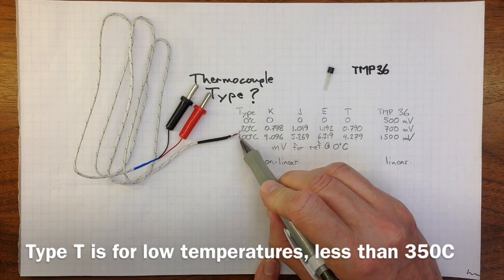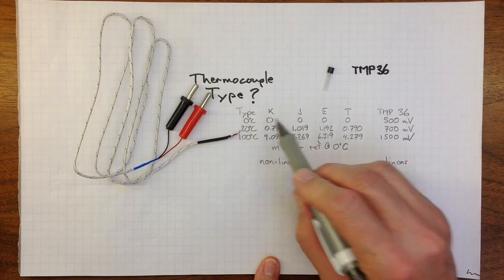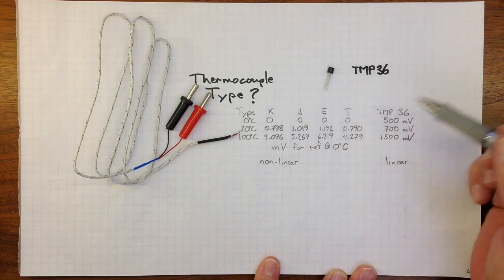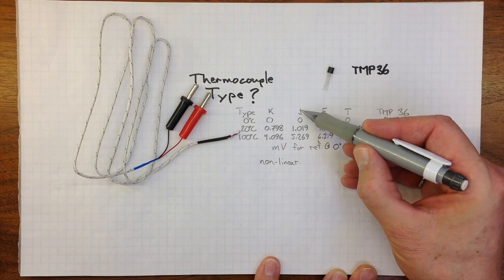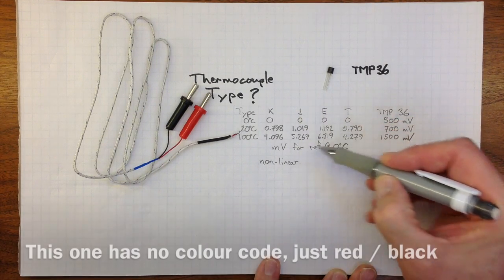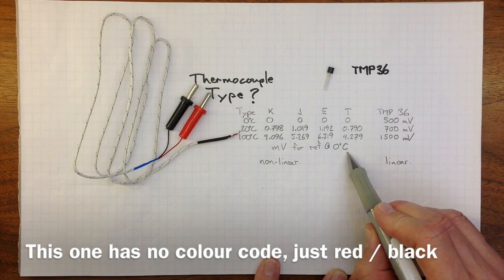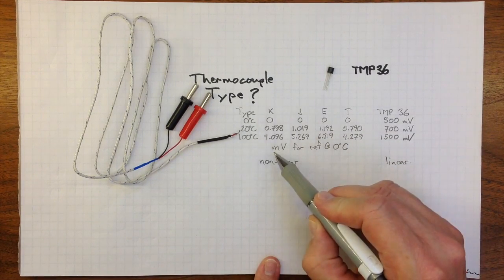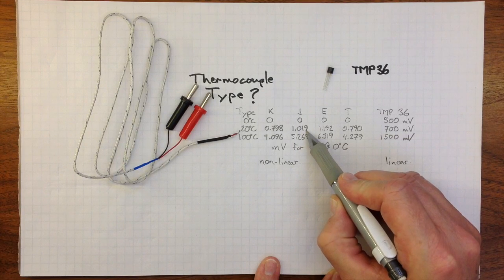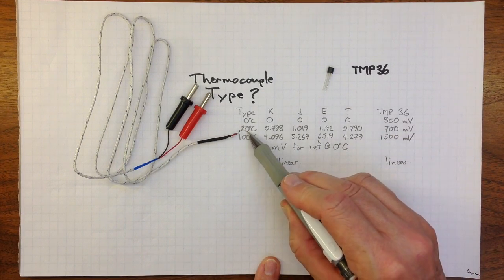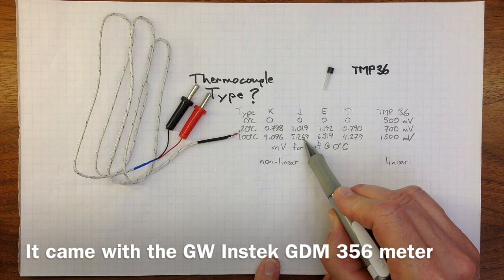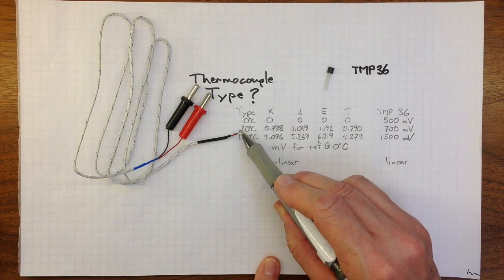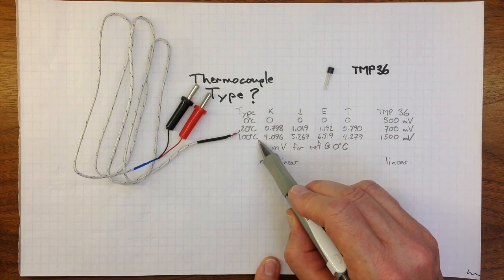Different metals give different potentials from the thermocouple. So if, for example, this was a type J thermocouple, we'd expect to see with the reference junction at zero degrees Celsius, no voltage if the bead was at zero degrees Celsius, or about a millivolt if the bead was at 20 degrees Celsius, or a little over five millivolts if the bead was at a hundred degrees Celsius.